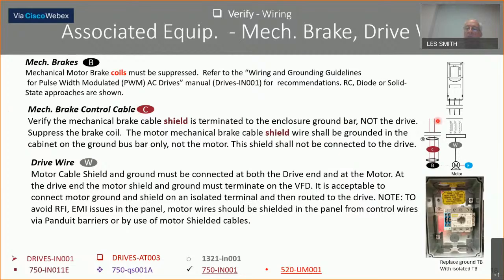Mechanical brake control cable right here. Again, they're going to talk about the shield and it not go to the drive, go to the backplate ground. Drive wire, that's this wire right here. This is the first time we've mentioned this. The cable, shield, and ground must be connected to both the drive end and the motor end. And daily, I find that you're not connecting the shield at both ends, along with the PE wire. And this is a different philosophy than when you're putting in instrumentation wire, etc. You only connect the shield at one end, source end of power, in that industry. We connect it on both ends. We want a path for noise to go through.